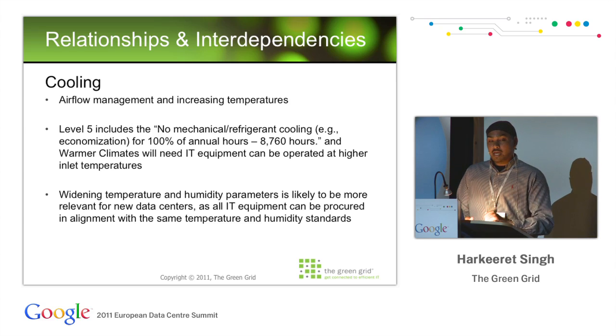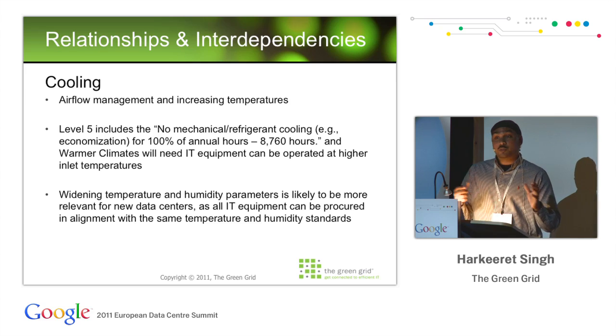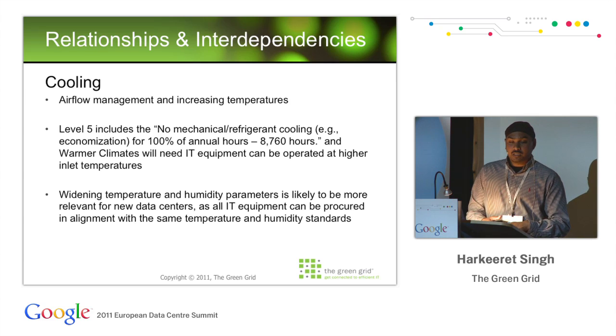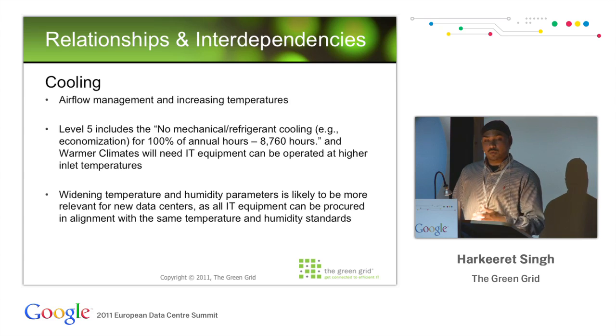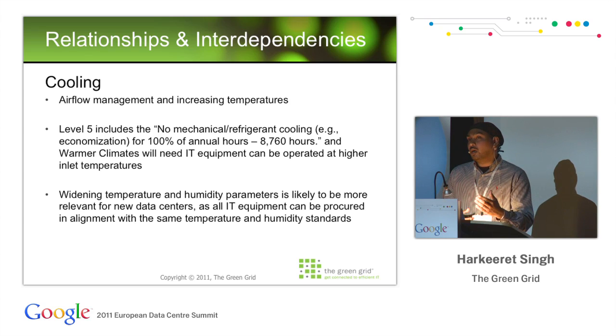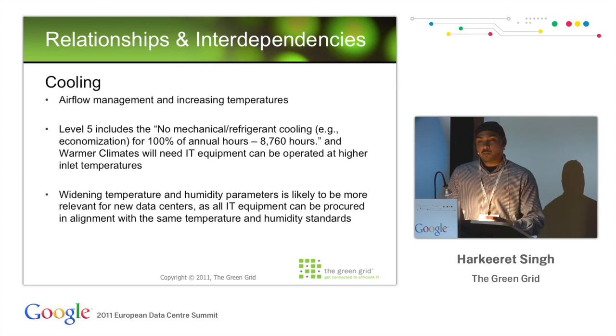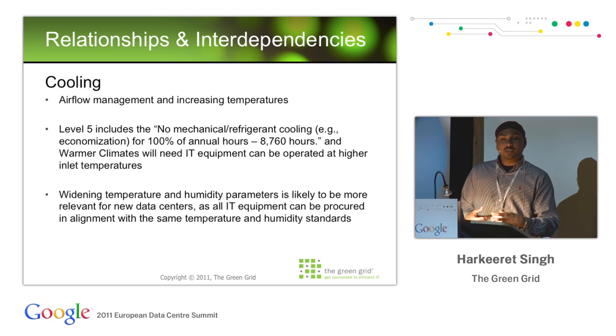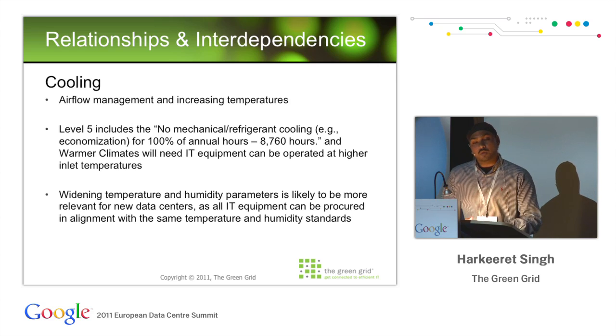Level 5 on no mechanical refrigerant cooling is 100% of annual hours, so 8,760 hours. Warmer climates will need IT equipment that can operate at higher temperatures, but we'll also need to see some cooling innovation. The last interdependency is that widening temperature and humidity parameters is likely more relevant for newer sites. As mentioned, with the fan power curves you can make sure all IT equipment is procured in alignment with the same standards, minimizing the impact of fan power changes.